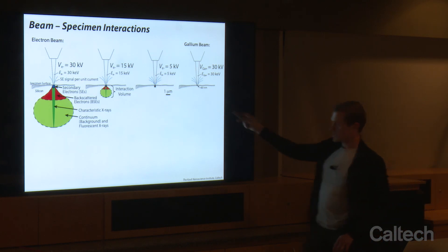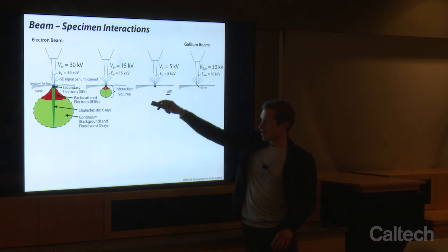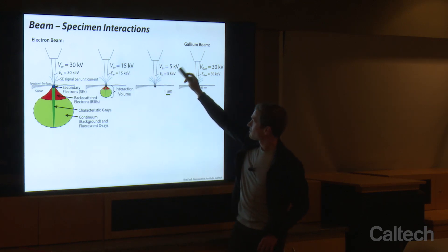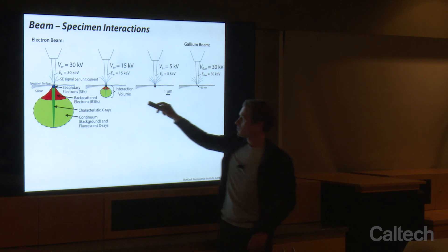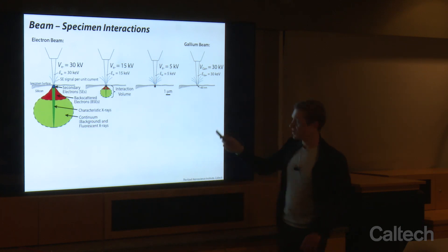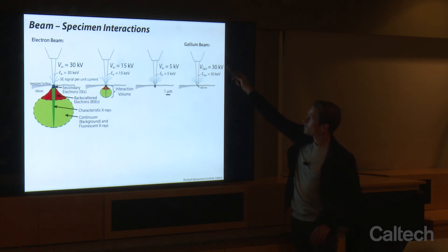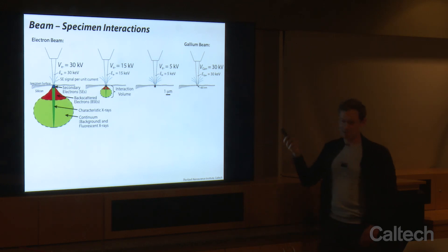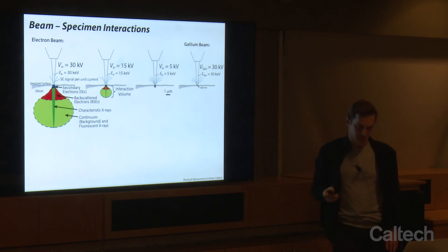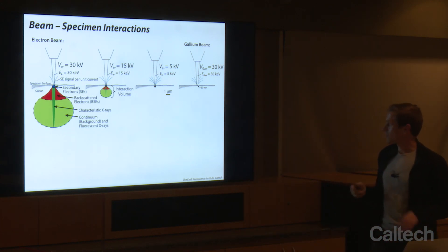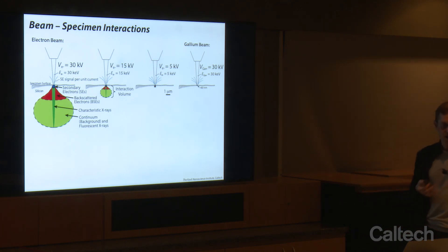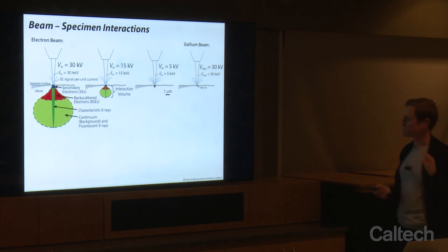In the SEM lecture, I spend time talking about interaction volume — this is in silicon at 30 kV, 15 kV, and 5 kV, giving about 8 microns of penetration into silicon at 30 kV. When we have 30 kV with gallium, the stopping power to these ions is great and you only penetrate about 60 nanometers into silicon. So the beam-specimen interactions are happening on very different orders of magnitude in terms of length scale.